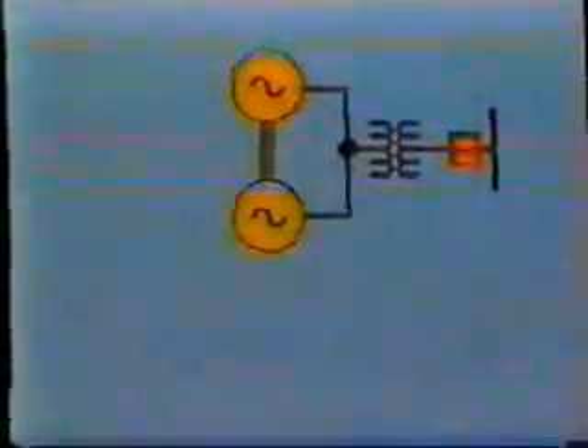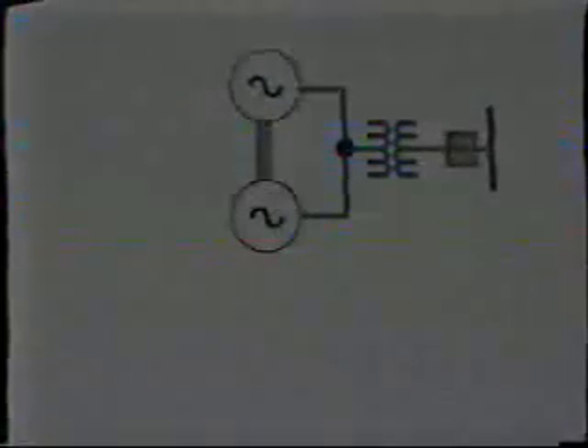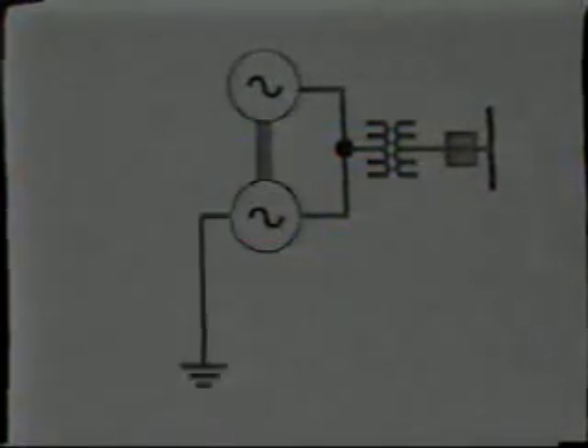We earlier mentioned compound or tandem generators, which are driven by the same prime mover system. Where the two generators are connected to a common unit step-up transformer, it is usual to ground only one generator neutral and install ground protection here. In case of a fault on either generator, both units will be tripped by the single protection.